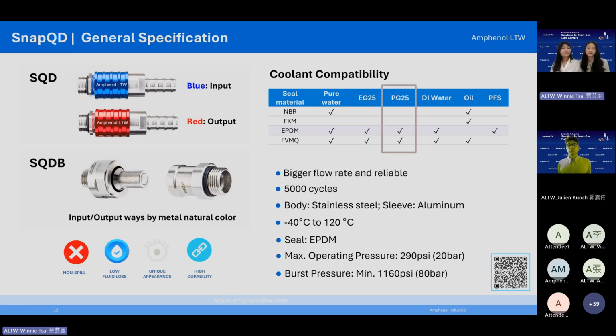Correct. And you will also see SQDB in our lineup. What does B stand for, and what are the differences between SQD and SQDB? Oh, it's a good question. The B stands for blind mating. SQDB uses a natural metal finish, no red and blue sleeves, and it's the blind mating version for UQD. It's designed for self-align and connect without precise manual guidance, where access is limited or modules are frequently swapped. So the rest of the features, such as 5,000 cycles, temperature range, and the material of the seal are all the same as SQD, right? Exactly.